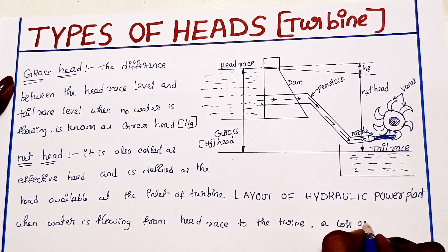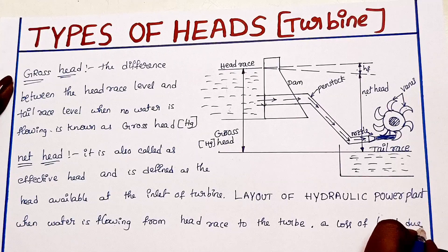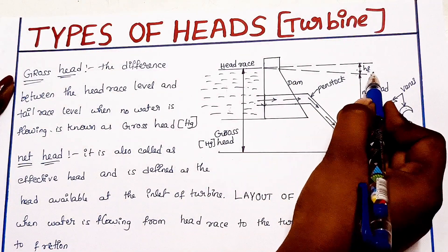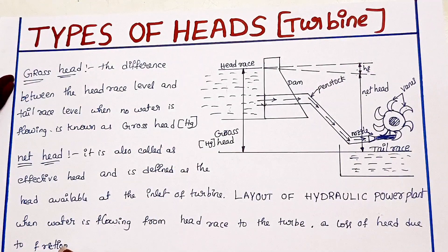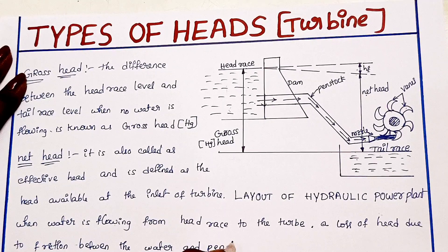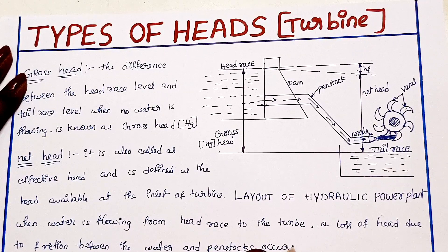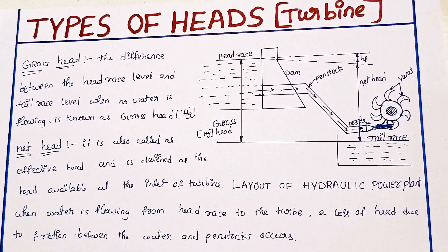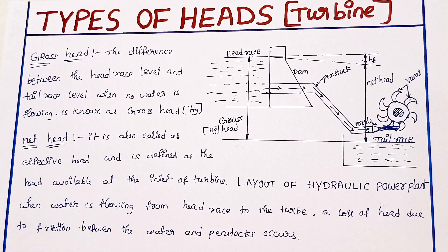When water flows from the headrace to the turbine, there is a loss of head due to friction, denoted as HF. This head loss due to friction occurs in the penstock — the large cylindrical pipe through which water flows. The head available at the turbine inlet after subtracting HF is the net head.